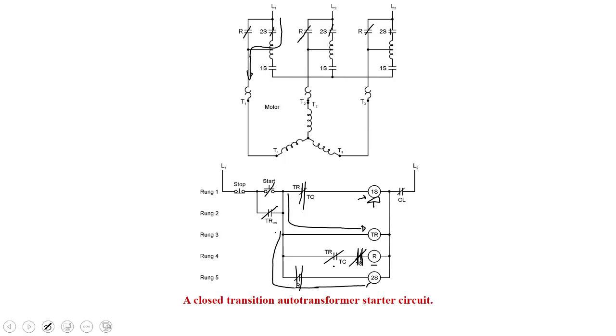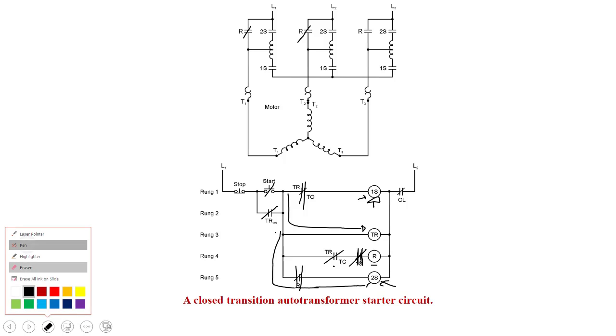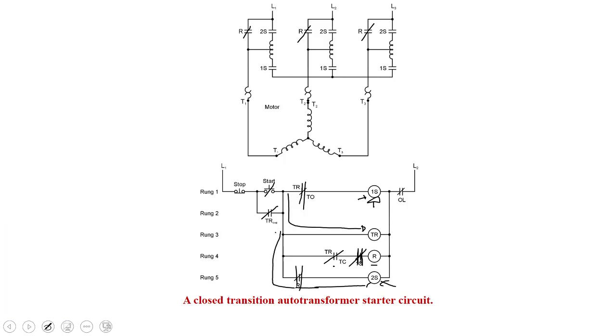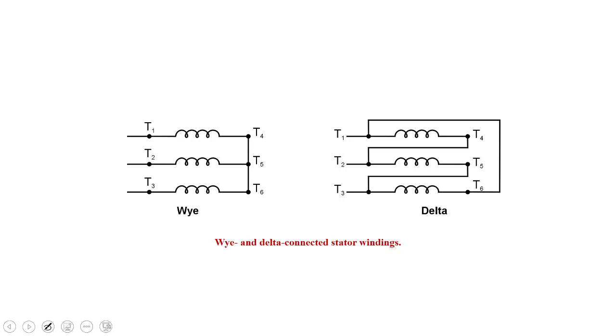So this goes to open, 2S would then de-energize. So no path there anymore. And we're at full voltage now going to the motor. The auto transformer windings aren't being used. So that's a closed transition auto transformer. We got one of these in the lab that we're going to show you as well.